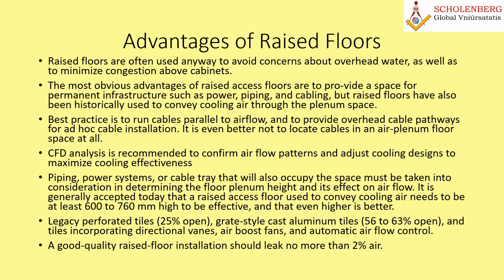There are several queries: why raised floors? Why should we have a raised floor and a plenum below the machines or below the servers and pump the air through the plenum below? Why should we do that? What is the advantage of a raised floor? Why not directly pump the air from the top in ducts and distribute it to the machines? So what is the use and what is the advantage of a raised floor?